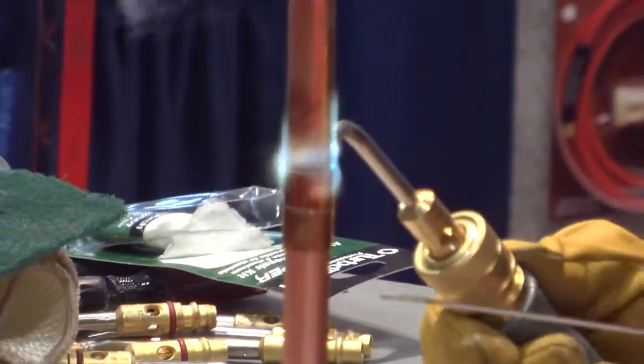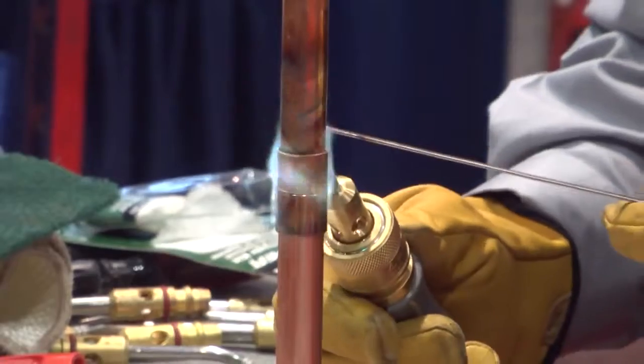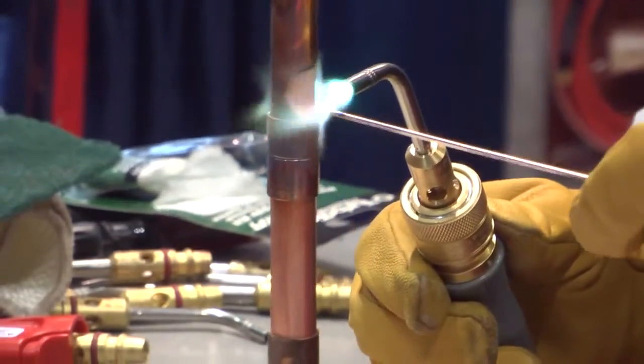As I move it around a little bit, I'm going to watch for the copper to start to turn color, and then I'm going to add the rod. By adding the phos-copper rod to the fitting, this will give you a good indicator that the copper is hot enough where it can actually start to braze.